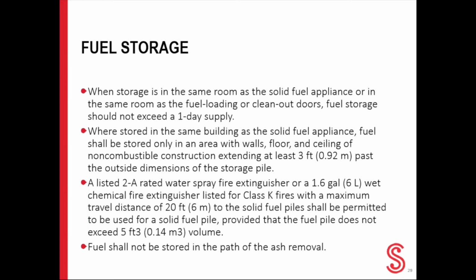What if you have more than 1 day's supply of fuel? Well, that's a very common thing that we see, and it is acceptable to store your over 1 day's worth supply of fuel in the building if your sprinkler system allows it under NFPA 13. This must be a design in the sprinkler system itself to have that ability to cover fuel of that magnitude. It is also okay to place it against a masonry exterior wall or outside the building at least 10 feet away. Solid fuel piles require fire protection.